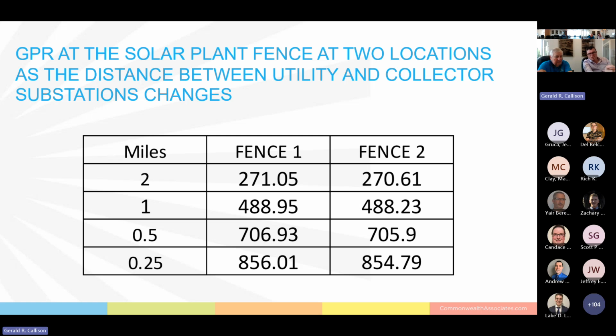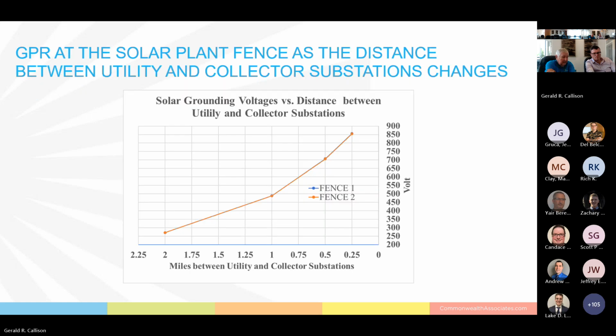Well, if you are designing this and it's 2 miles away, it may be safe at the solar plant because the touch voltage may be below the tolerable. But if it's only a quarter mile away, then the voltage is up to 855, and that may not be safe. So in one instance where it's 2 miles away, it could be safe, and if it was closer, it may not be. So again, for us visual folks, if you look at the graph, this shows that the voltage is going up from about 255 up to about 850.